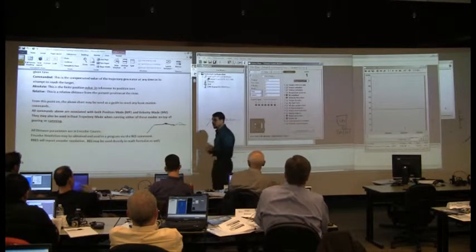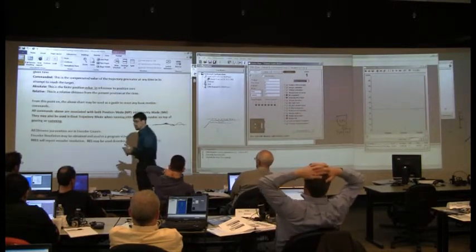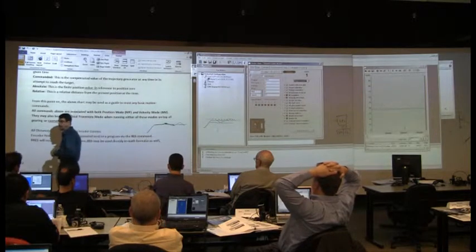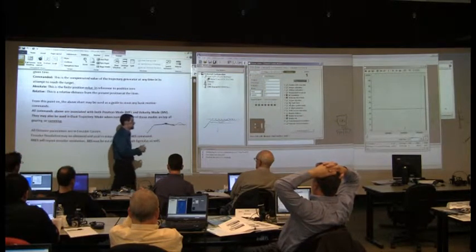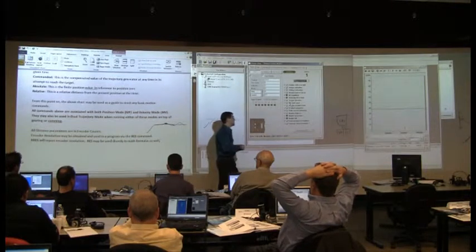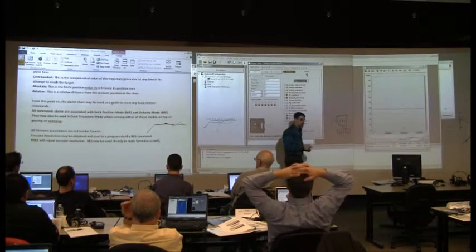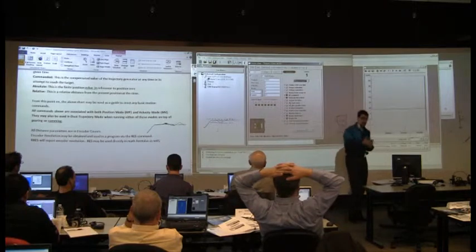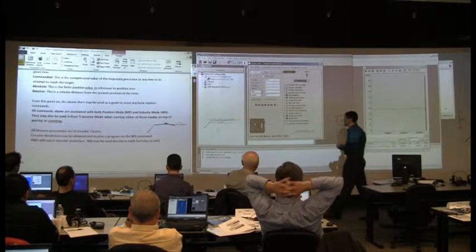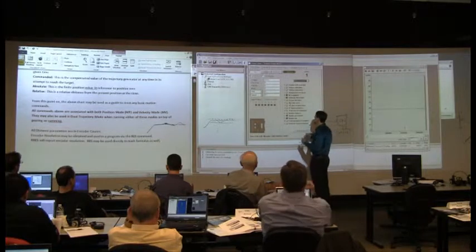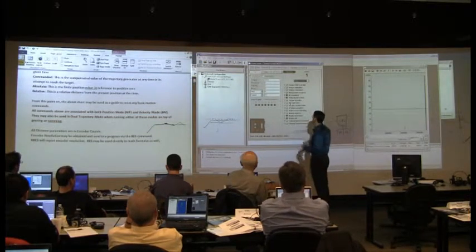Torque direction's the same way. You can actually be going in the positive direction and be commanded a negative torque trying to slow down. So that bit can be on or off in either direction. It doesn't matter. It's basically telling you which way it's trying to go compared to where it's actually going. Am I trying to speed up? Am I trying to slow down? Am I trying to add more force or subtract from that force? That's what these give you.